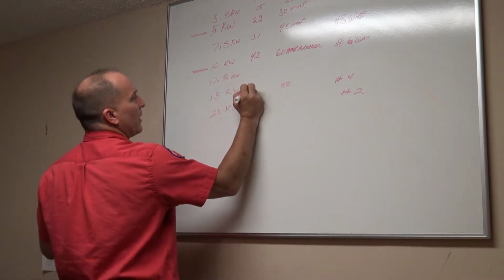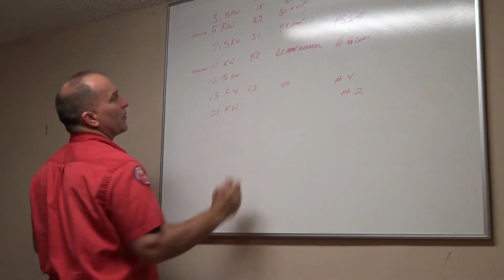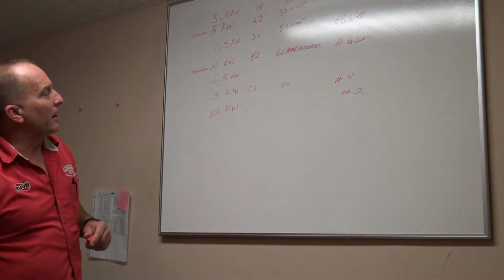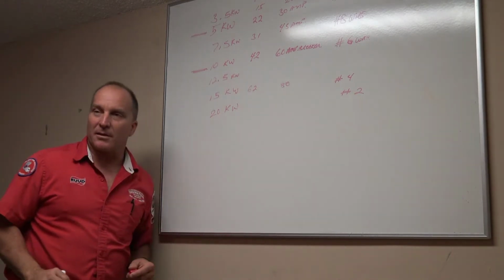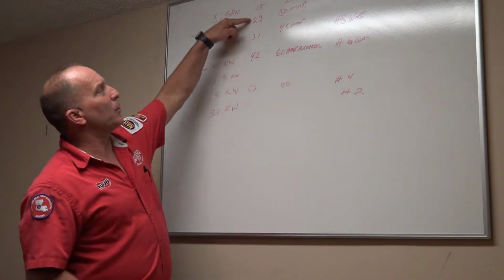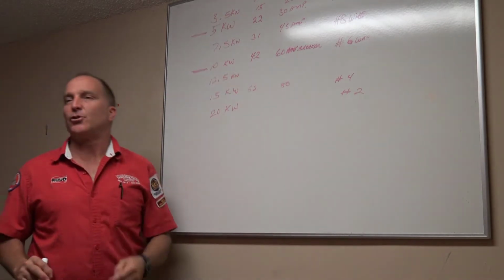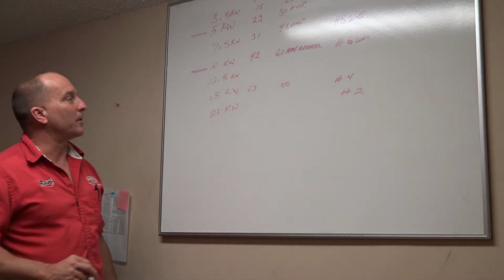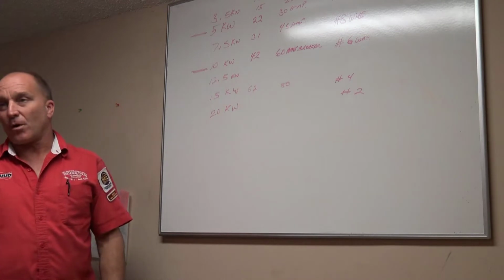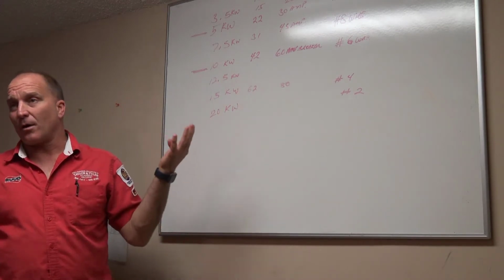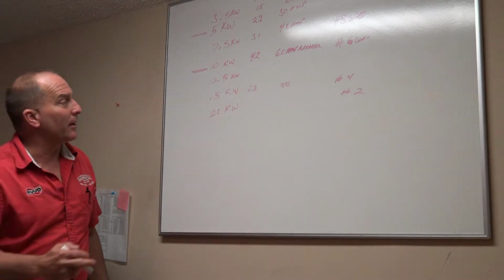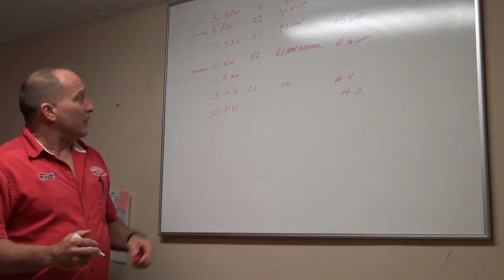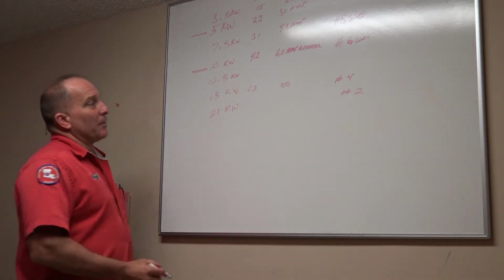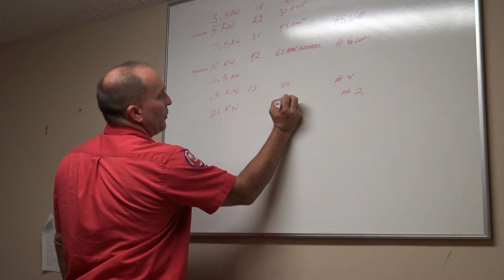You're somewhere in the neighborhood of about 62, 63, 64 amps in there for a 15 kW heat system. Remember, part of this amperage draw is actually your blower motor, not just the heating element by itself, okay? Because when you take your amperage draw, you've got to take the amperage draw of the whole system, right? It's got to have your blower motor in there. All right, 20 kW. Well, I've got number 2 wire now. That's going to be a 100 amp breaker.